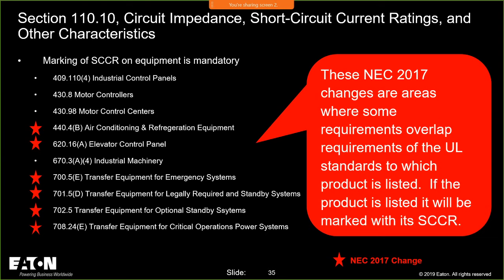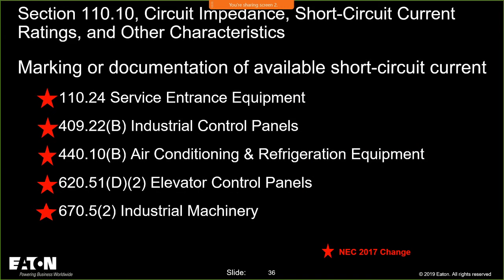The elevator control panels, industrial machineries, and air conditioning are all types of UL 508 equipment, industrial control panels that will be marked with a short circuit current rating if it's a listed control panel. Motor control centers, motor controllers, and industrial control panels will all have the short circuit current ratings marked on them based upon the standards to which they are listed.